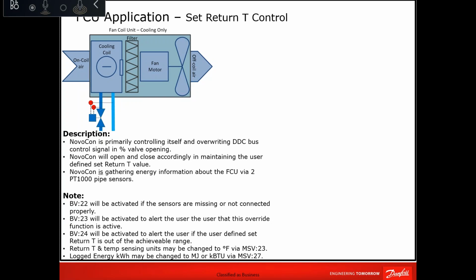So you might ask why you need this and why you need that. Let's take an example. If you will be using this actuator on a pipe branch, there is no local control, there is only BMS control, and you need to maintain the delta T on that. So you enable set delta T control on that branch, and that's it. But if you are using the Novocon to control a unit as a normal operation and you have doubts on what will happen with the delta T, then you can use minimum return temperature or minimum delta T control. In case of minimum delta T or minimum temperature control, you will maintain the local control, which is via thermostat or BMS locally, plus you will be able to control based on the delta T in case it's dropping below the set point.